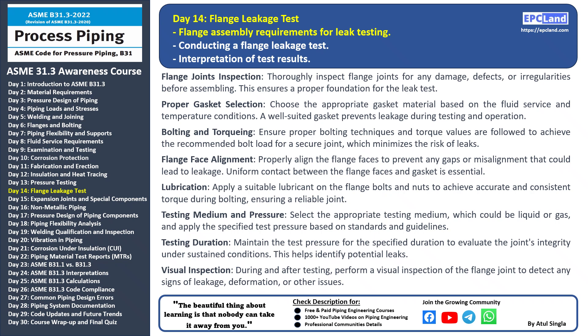Flange face alignment: accurate alignment of flange faces is important to create a uniform sealing surface — misalignment can lead to uneven pressure distribution and potential leaks. Lubrication: apply lubrication to the flange bolts and nuts before torquing to achieve accurate and consistent bolt loading. Testing medium and pressure: select the appropriate testing medium (liquid or gas) and apply the specified test pressure according to industry standards.